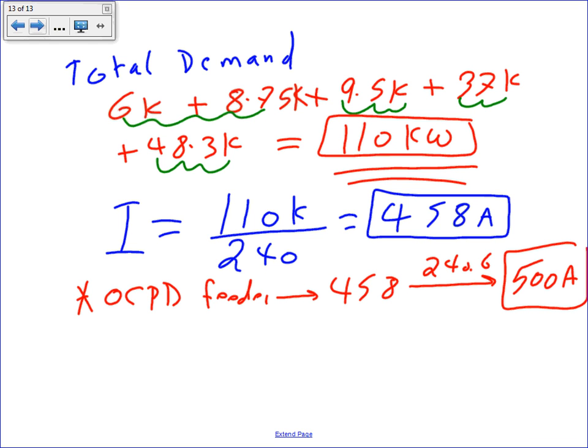Now, Phil, here's the moment of truth. You either size the cables based on the 500, which engineers will do, or contractors, to cut cost, up to 800, we can size based on what? That size, the actual size. Okay? So, let's go feeders. The second one is feeder size. Okay, feeder size. I'm going to size it first based on 458 amp.